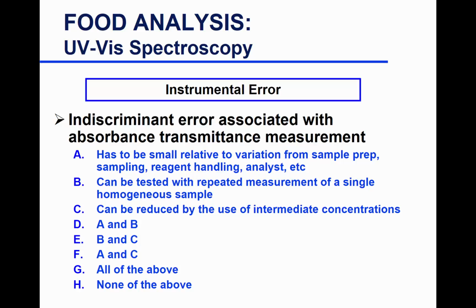So typical absorbances usually are between 0.8 to 1. 1.2 is sometimes acceptable, but if you have absorbances that are 0.02, for example, this is very close to your blank, very close to the noise. So you don't want that. And if your absorption is reading 1.3, 1.4, or 2 sometimes, you are probably outside of the linear range.